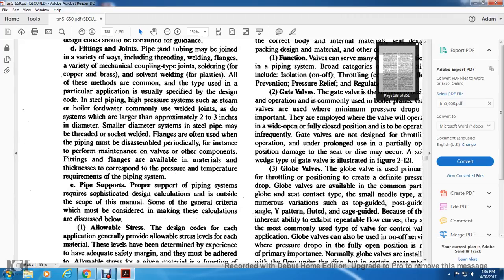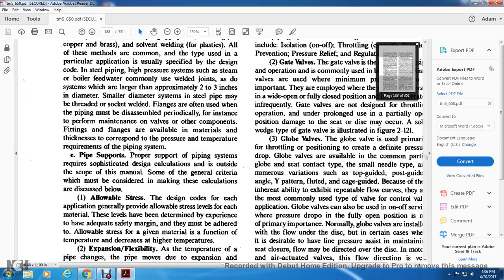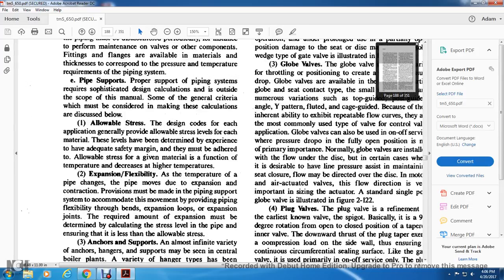Pipe supports for the piping system require sophisticated design calculations outside the scope of the manual. Some of the general criteria that must be considered in making these calculations are discussed below. Allowable stress. The design code for each application generally provides allowable stress levels for each material, which must be determined by experience to have an adequate safety margin. They must be adhered to given the material, the function, the temperature, and the decrease in allowable stress at high temperature.